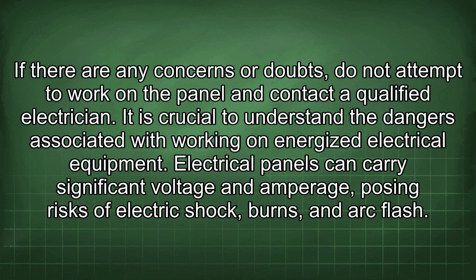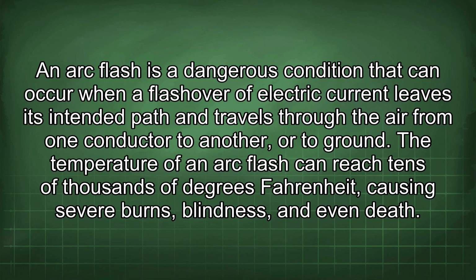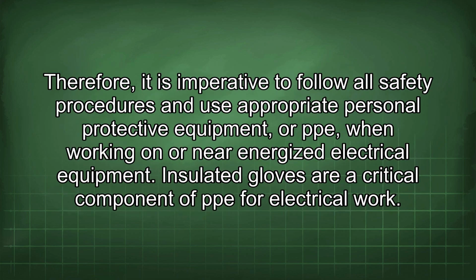It is crucial to understand the dangers associated with working on energized electrical equipment. Electrical panels can carry significant voltage and amperage, posing risks of electric shock, burns, and arc flash. An arc flash is a dangerous condition that can occur when a flashover of electric current leaves its intended path and travels through the air from one conductor to another or to ground. The temperature of an arc flash can reach tens of thousands of degrees Fahrenheit, causing severe burns, blindness, and even death. Therefore, it is imperative to follow all safety procedures and use appropriate personal protective equipment, or PPE, when working on or near energized electrical equipment.